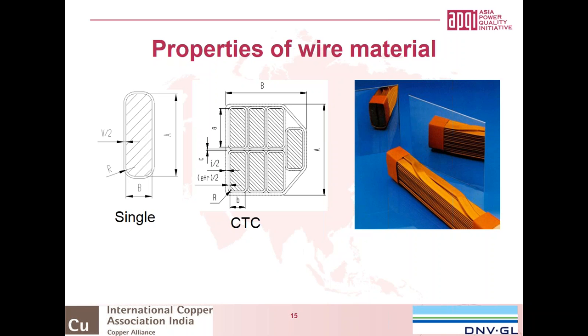If you look at what the eddy currents are doing within those, the magnetic field, I already told you about it, and also the harmonics, which produce a lot of things. You can imagine that the smaller the area is, the smaller the wires are, the fewer eddy currents you have. So it depends a little bit on the transformer manufacturer whether he is selecting the CTC, continuous transposed cable, or doing one wire. You will see that immediately when he uses CTC, the amount of extra losses within a transformer will reduce.